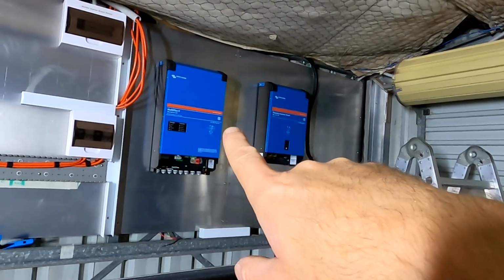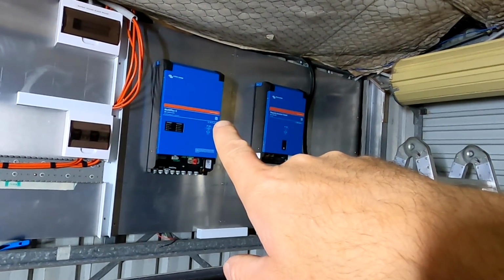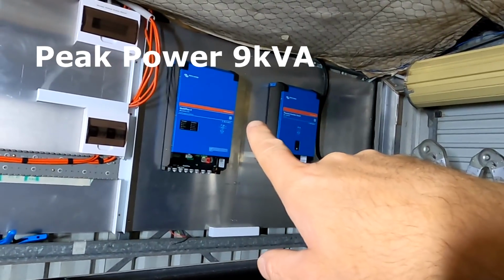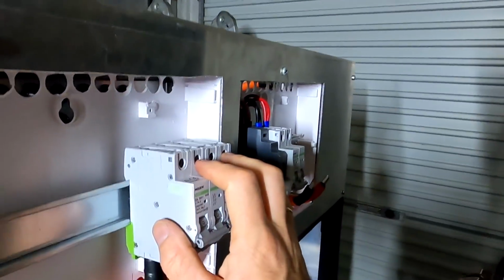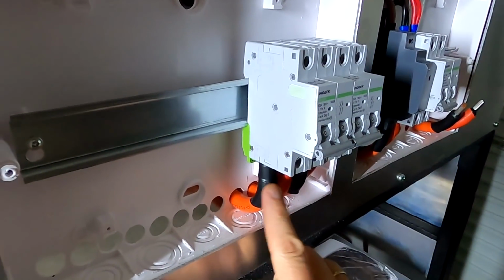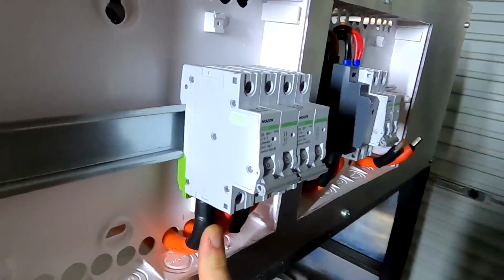Because this beast is able to put out, I think, 10 kVA for a couple of seconds when you start motors and everything. And you don't want to have your circuit breaker tripping all the time when this happens. So it needs to be at least 125, better even 150. And there's no circuit breaker out there with DIN rail mounting capability in this size, with 150 amps and 35 millimeter terminals.